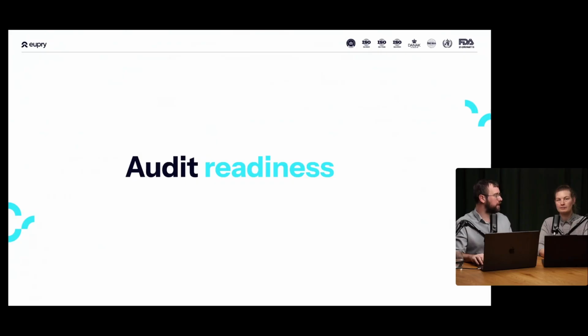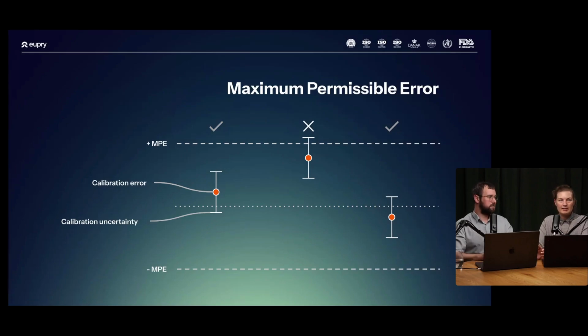So moving on a bit, how should you be ready for an audit then? I think we have a question here about the risk assessments. Could calibration be done every 2 years instead of 1 year? The answer is yes, it could. Again, it's a point in time measurement, but it's all to do with your process. And if you pull up the picture from before, if you have any risk assessment saying that your sensor might drift out of this specification and move towards the one with the little X in the middle here, then it's probably better that you do the calibration every year or maybe even more often. And we'll deep dive into this trend analysis right here.